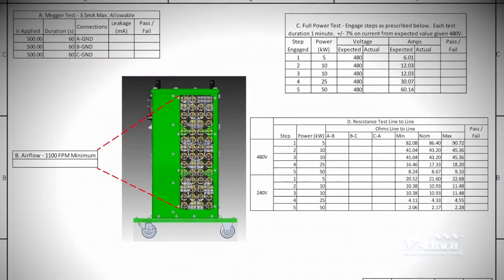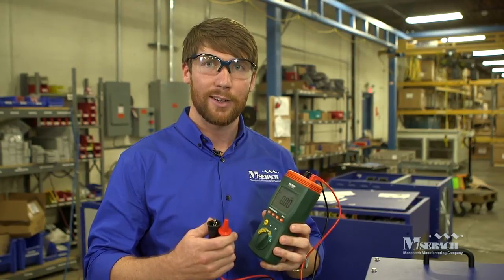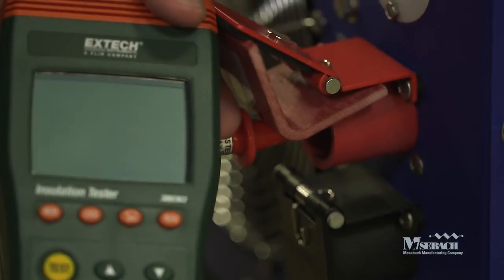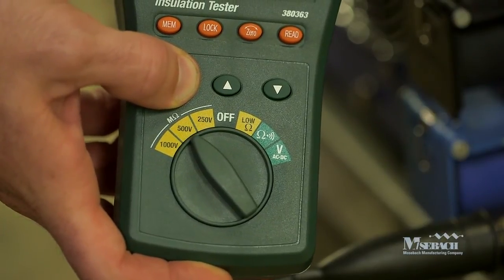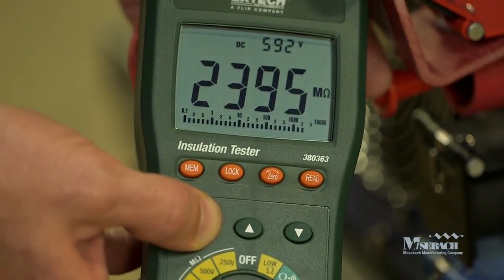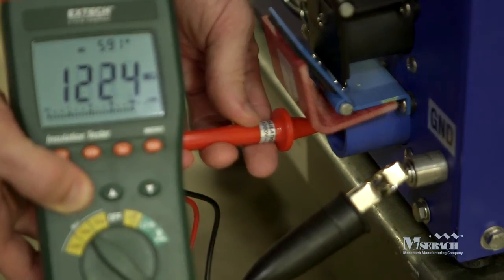Now that we've shown you how to set up and operate your load bank, we'd like to show you some tests to periodically check that your load bank is in good working order. These four tests are all documented on our X100 customer checklist. The first test is a Megger test, designed to test the insulation from the power circuit to ground and detect any electrical shorts. We recommend the Extech Instruments Insulation Tester Model 380363. Connect the black lead to ground and touch the red one to the A phase cam lock, then set the meter to the 500 volt setting. Press and hold the test button for several seconds. You'll see that the resistance exceeds two mega ohms, indicating a large resistance from the power circuit to ground — this is a good thing. If this number were low or approached zero, there would be reason for concern. Repeat the Megger test from B phase to ground and from C phase to ground.